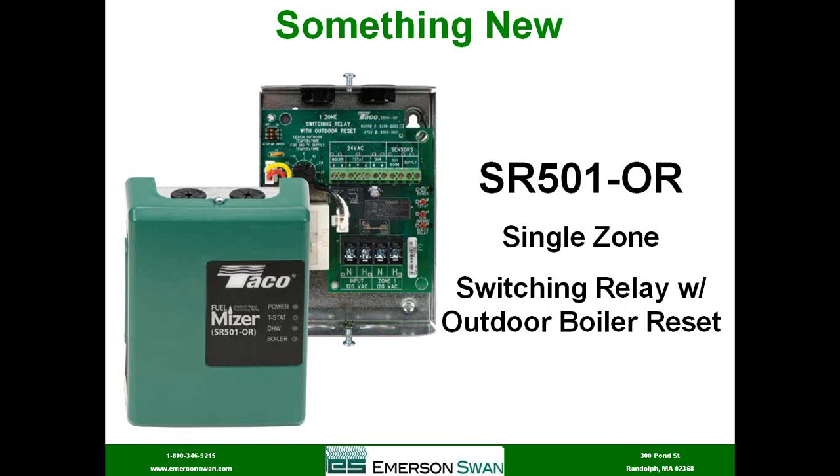Basically, we're going to put that between our dumb boiler and whatever was telling our dumb boiler to turn on. That's probably the easiest way to explain how this is going to work. Something is making that boiler go on. It's a thermostat operating a relay, which is then operating an end switch going to the boiler, or we've got zone valves. Whatever was telling that boiler to turn on is now going to hook up to this, and then we're going to go from here to the boiler.